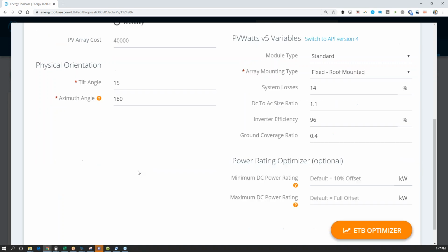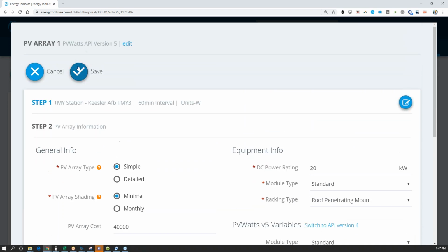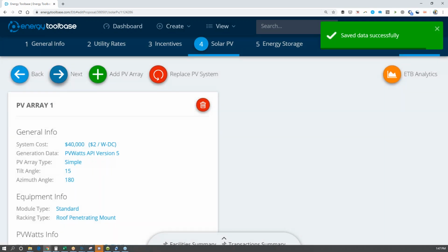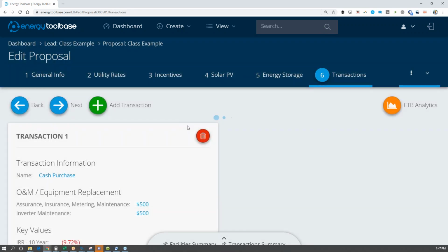And so what we need for our project is to have a payback that is within reason, and that's going to be like a 20 kilowatt array installed at $2 a watt. Something smaller than that would have too high of an installation per watt price to be economically justifiable. Something that's larger than this would have to have even lower installation price.